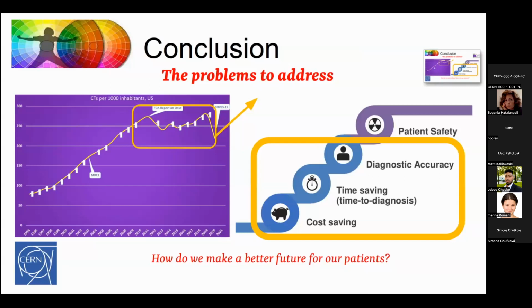And the third aspect is actually simply to do with the mechanics of the old integrated detectors. They were crystals, cesium iodide, I think, and each pixel would have a little boundary between it, not the non-scintillator, otherwise the light in one pixel would diffuse into the neighbor. And as those pixels got smaller and smaller and higher resolution, about a quarter of the detector ended up being the barrier between the pixels. So you've got about 25% dead space, and that goes. So there's 3 reasons that you're going to be able to lower the dose.